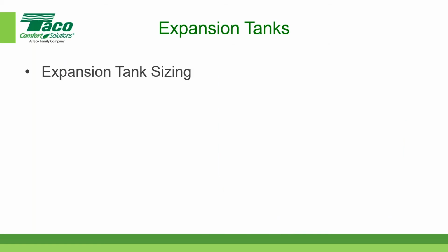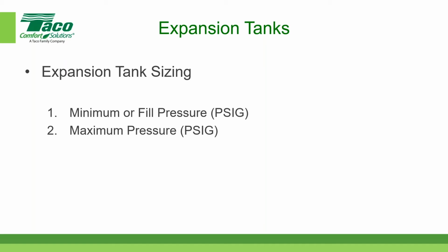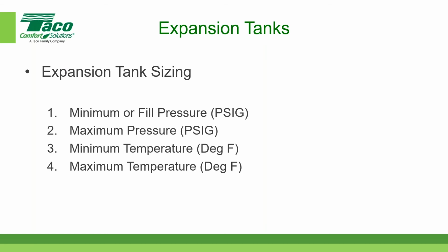Okie doke. So when it comes to expansion tank sizing, that's our next discussion here, then we have to account for 6 things, and I'll just run through the list. The minimum or fill pressure in pounds per square inch gauge, and this is the pressure at the expansion tank. The maximum pressure at the expansion tank, the minimum temperature of the system, the maximum temperature of the system, the fluid type, and finally, the system volume in gallons. Now, today's discussion is all going to be based on US units or imperial units.